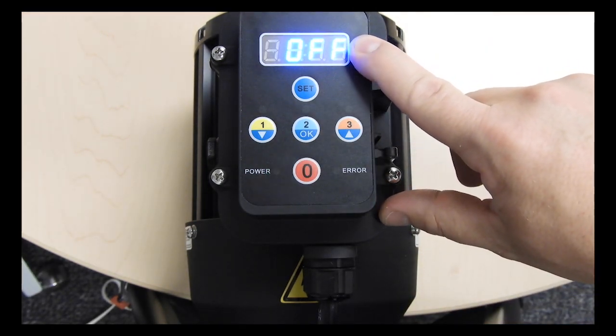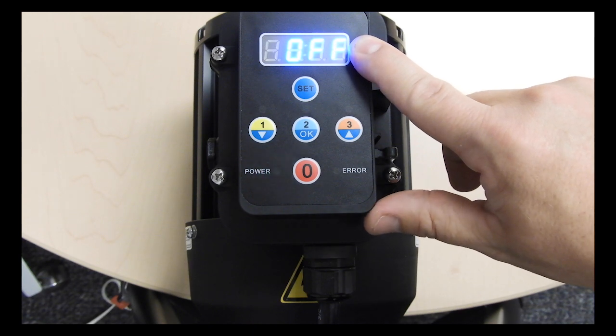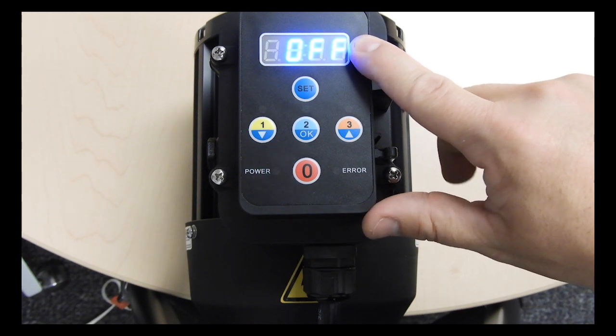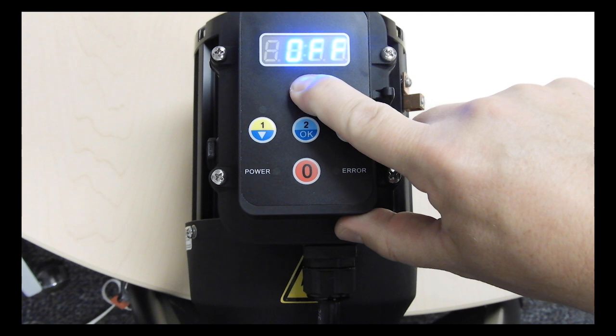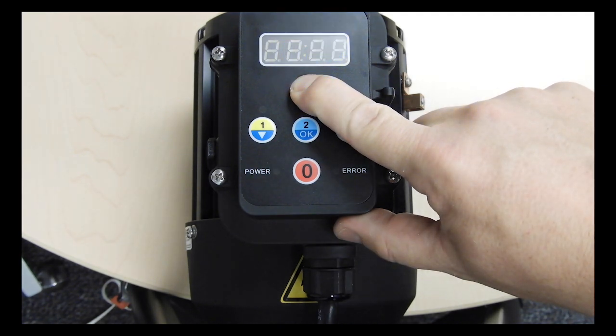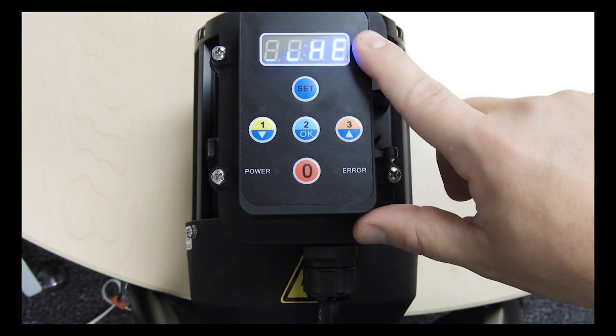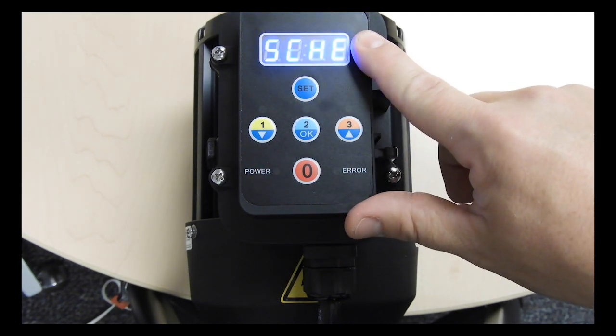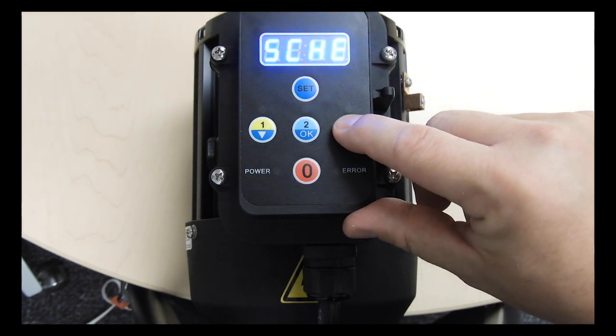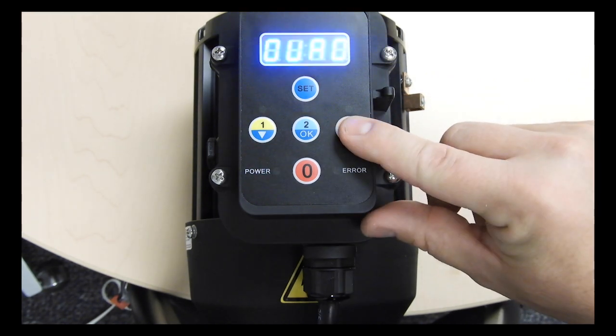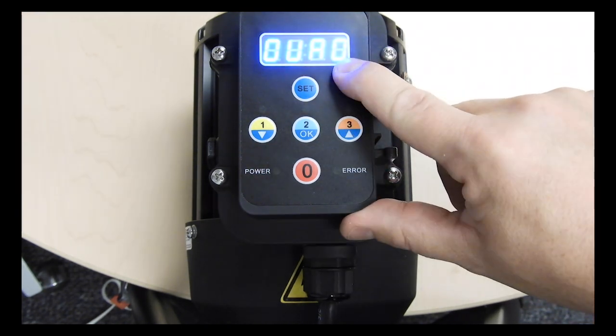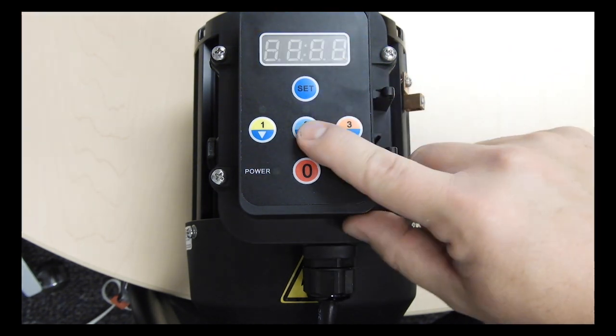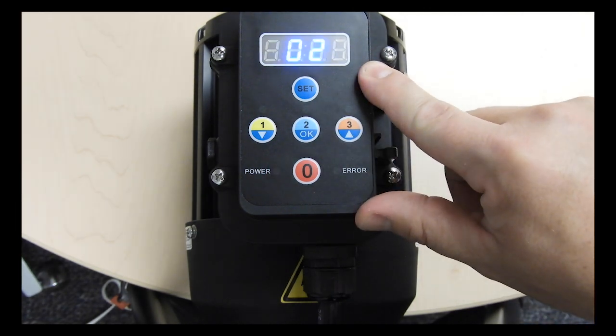Enter programming mode by pressing and holding the set button for at least 3 seconds. Once you see SCHE shown on the display, press the up arrow once and OVRD will be shown on the display. Press OK to enter the override menu.